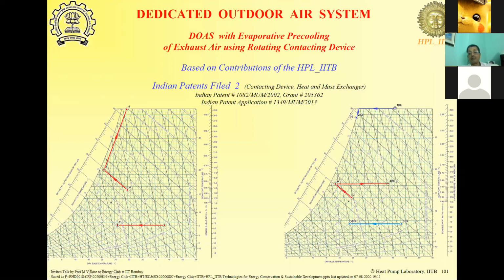in an air-to-air heat exchanger to cool this down here. Now, this is another heat exchanger where we are taking the room air and humidifying it. And then if we just do sensible heating, you are going to get this. But in this case, as you can see, if we go like this, then even with a much smaller flow rate of this air, we can cool a much larger flow rate of fresh air. And in places like Mumbai, where the temperature is moderate but the humidity is high, you can partially condense also with this type of thing. And even with this, it can be brought down further if you're going up like this.